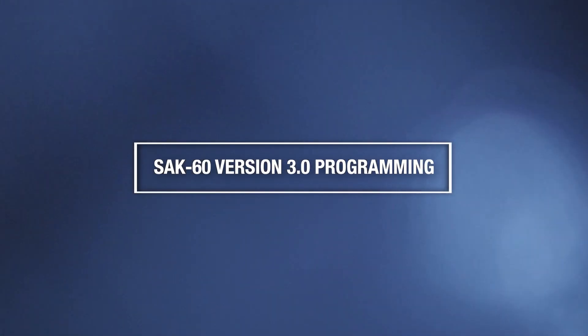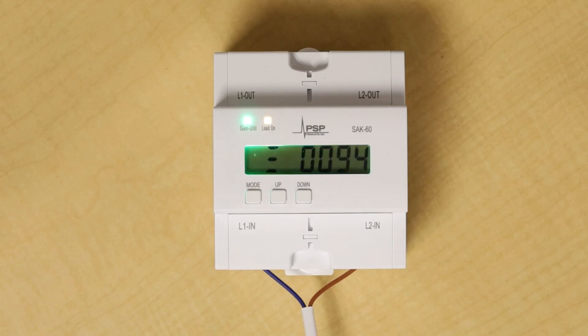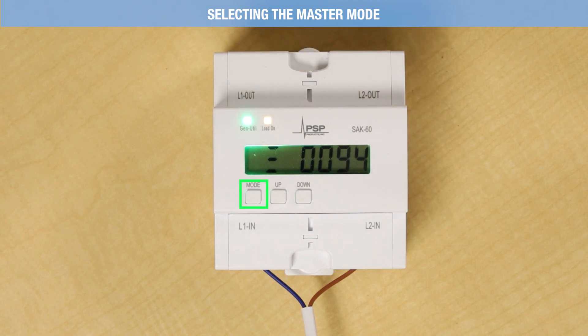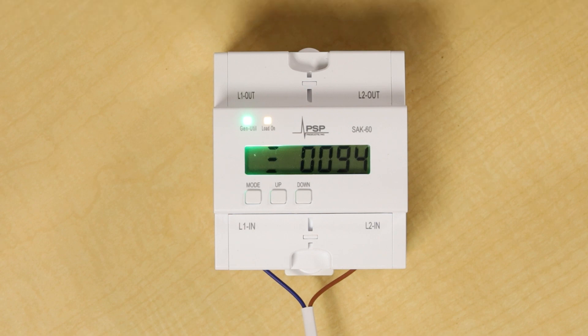To program the SAK60 version 3, you must first select the master mode that corresponds to your application. Hold the mode button for about 3 seconds until two digits appear on the display. Then press the mode button briefly to scroll to the correct master mode, then hold the mode button again for about 3 seconds to enter the programming mode. After you've adjusted the settings, leave the SAK60 alone for about 7 seconds, and it will save the changes and reload the programming with the new values.